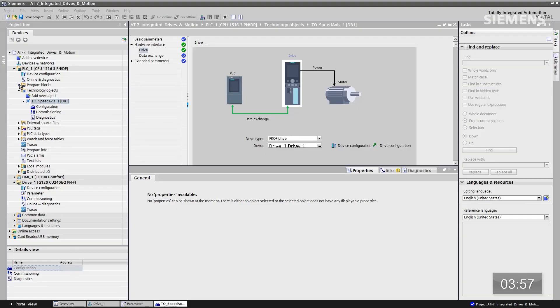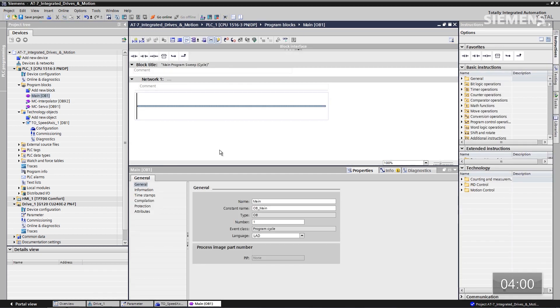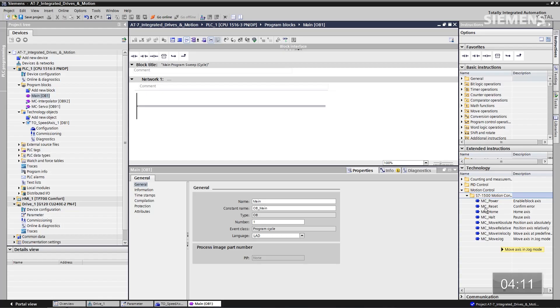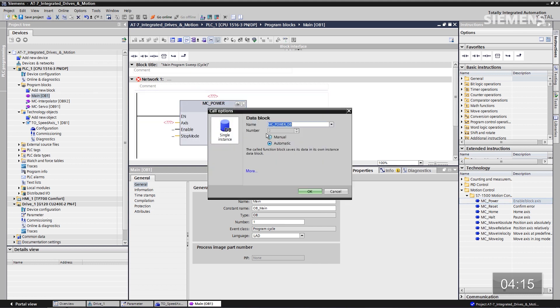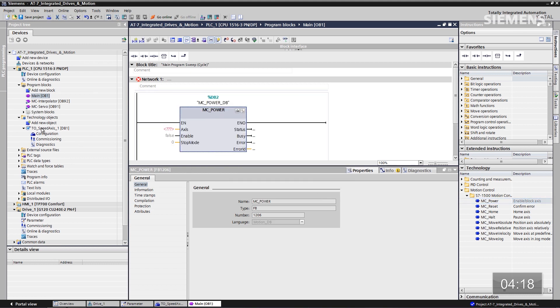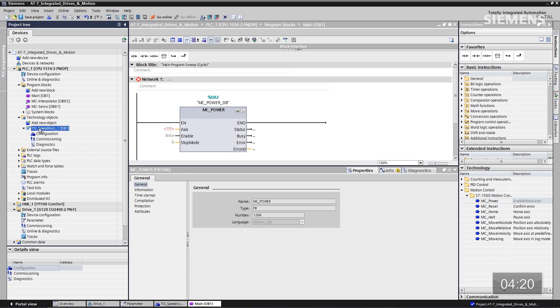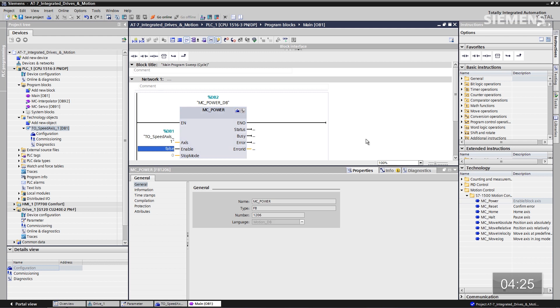So how about setting up the program? I want to come over to the program blocks, give focus to the main OB — as you can see, I have no current program in this controller. I'll come over to the Instructions in the Technology section for motion control, where the available PLCopen blocks are listed. The first one I'd like to use is MC Power. Drag and drop it into our program, accept the default data block, and tie this to our TO that we created for speed axis — drag and drop it over to the axis input. To enable this, I'm going to use input 0.0.